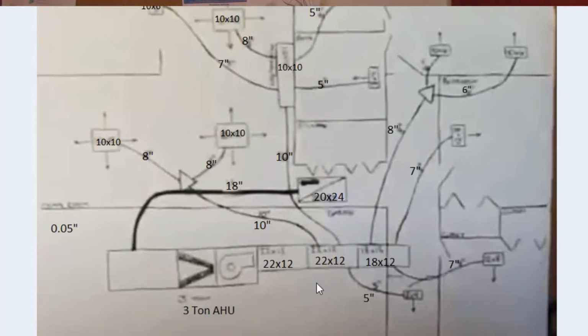Now, here's the thing. I went through and looked at his whole setup. These 22 by 12 main trunk sections are not too terribly bad. I mean, they're slightly large on the volume side. Our velocity is not really high, but that's fine. If my velocity is really low, I don't care. As long as it's not high, I'm fine with that. I'm not going to beat them up over the trunks themselves. But where I have an issue is looking at this critical path here.